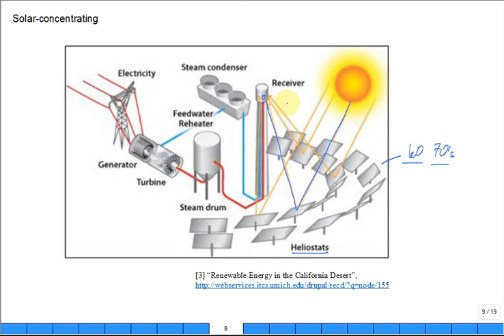Here they don't show it, but let me modify a little bit. You could take an oil or liquid metal and run in a loop down to a drum and then back up again. Why? Because you can really change the temperature of a liquid metal or an oil or something without boiling it. And if you boil it up there, then it's a lot larger volume and now you've got to have big pipes to bring the vapor down, where it's just small pipes to bring oil or liquid metal up and then liquid metal down again.